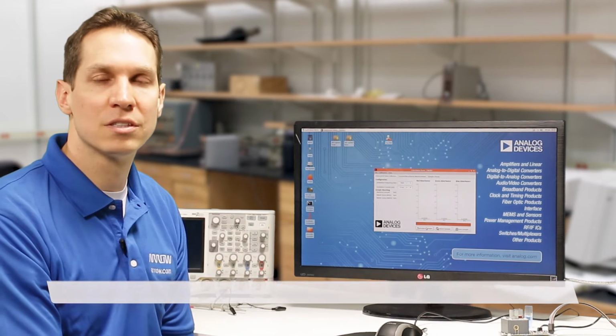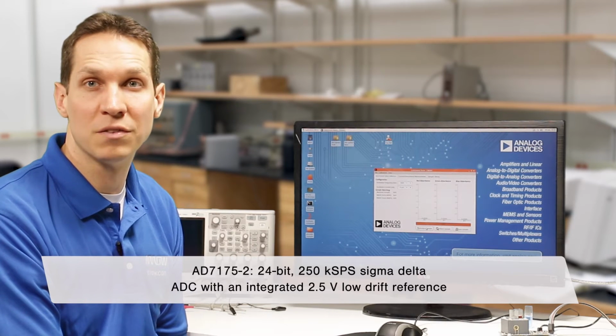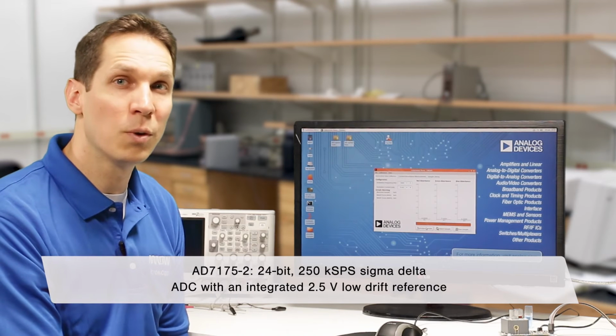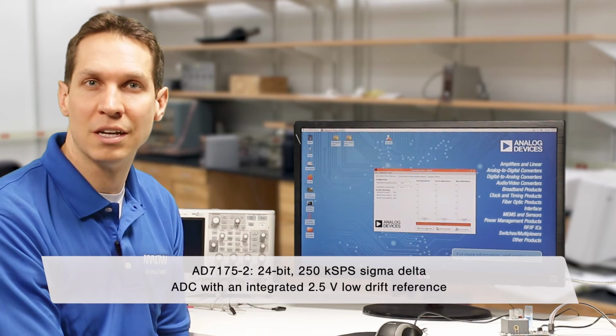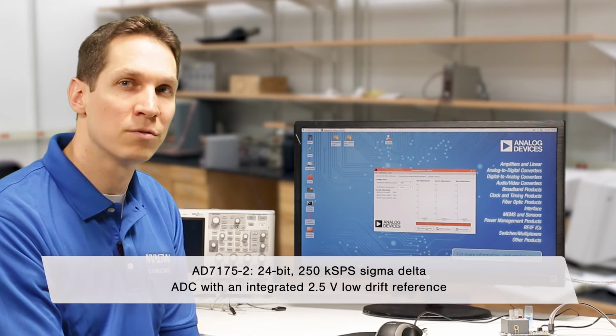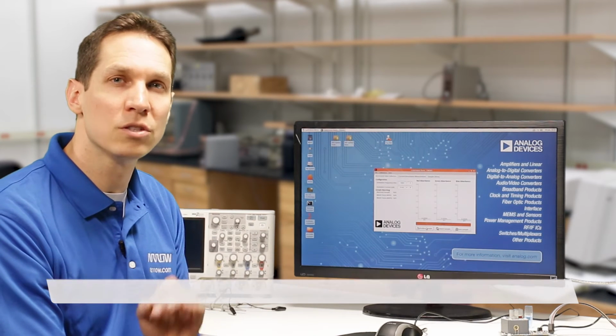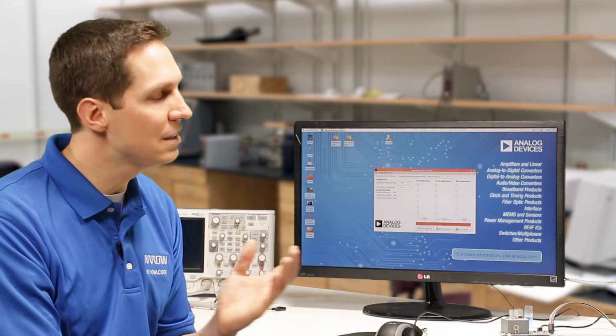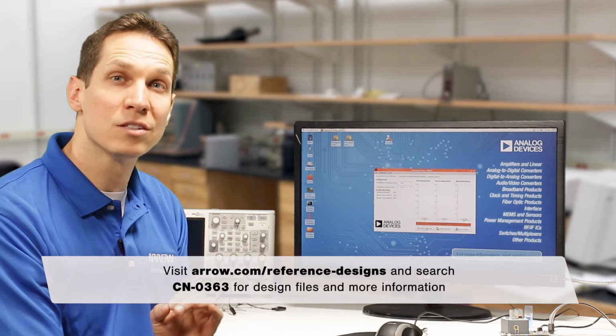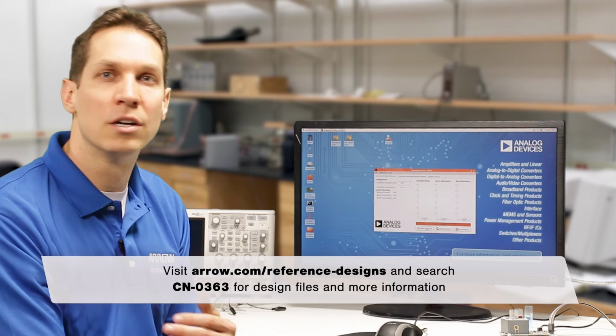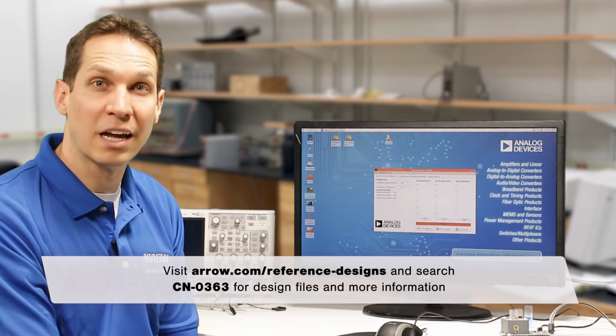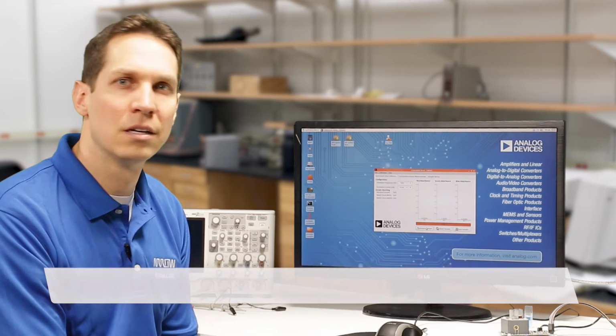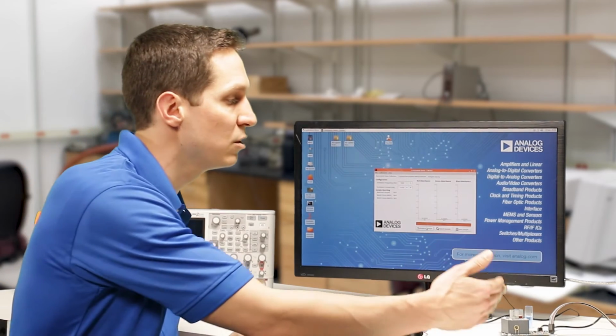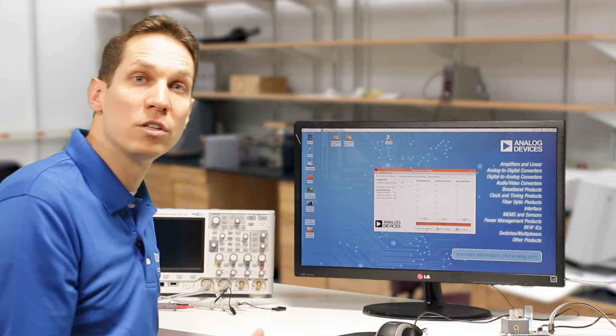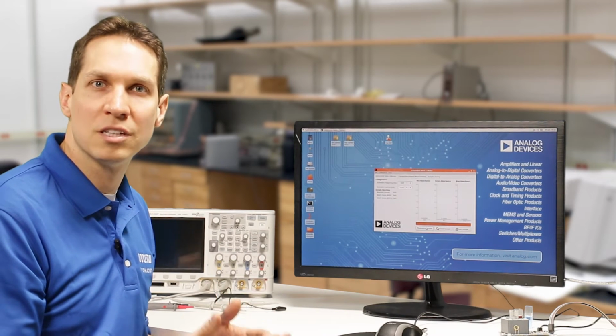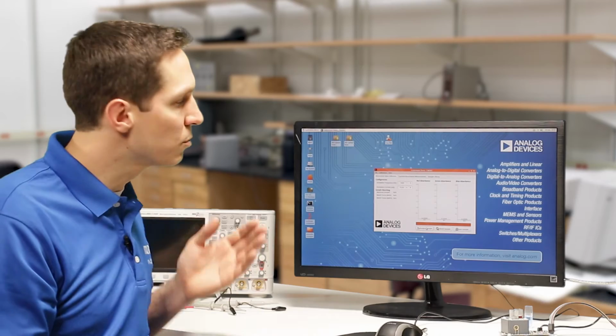For the CN0363, ADI uses the AD7175-2, a 24-bit, 250 kilosamples per second sigma delta ADC with an integrated 2.5 volt low drift reference. This is the only source of drift, and it is well specified, making it easier to account for in calibration. This combination of software with the right hardware reduces BOM cost, design time, and calibration frequency and complexity. So the sampled data is passed via the SPI interface to the FPGA, where the demodulation is applied to measure the light absorbed by the sample solution compared to the reference, and displays the results here on the screen.